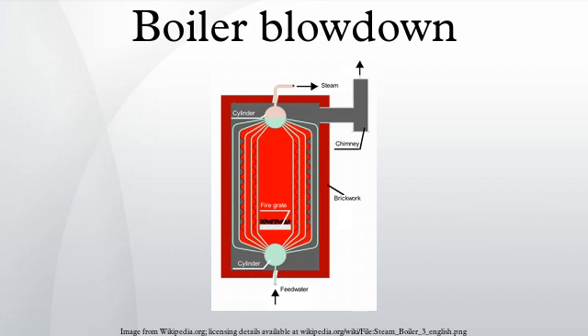Surface blowdown continuously bleeds off a low volume of water from within the boiler as a means of ridding the boiler of dissolved impurities. It is most effective to remove water with the highest level of impurities, and such water is found where steam separates in the steam drum at the top of the boiler.